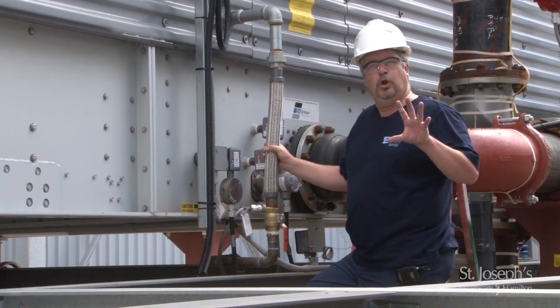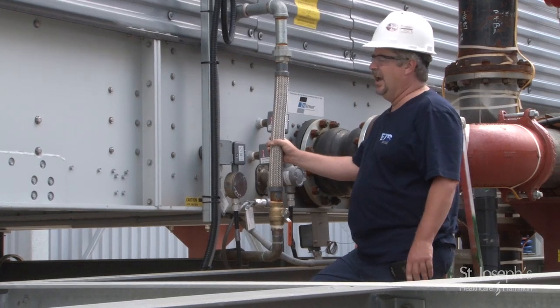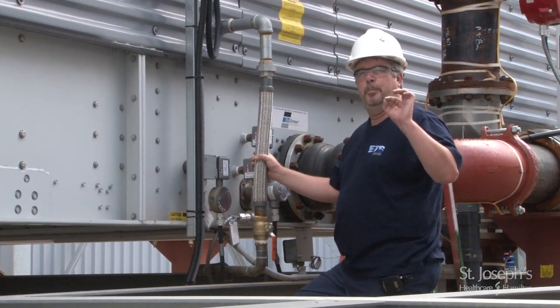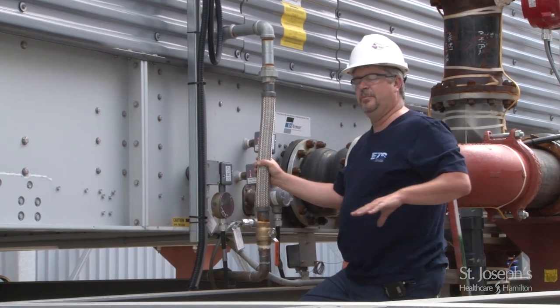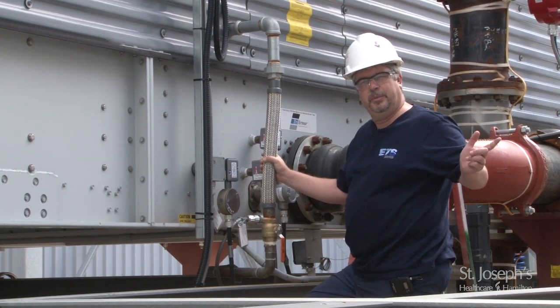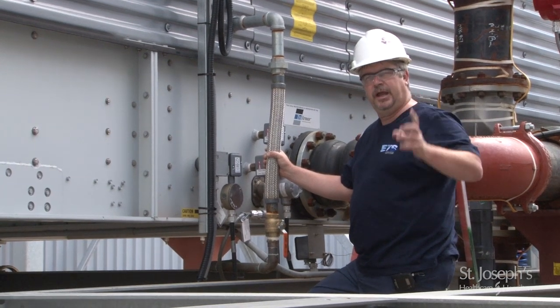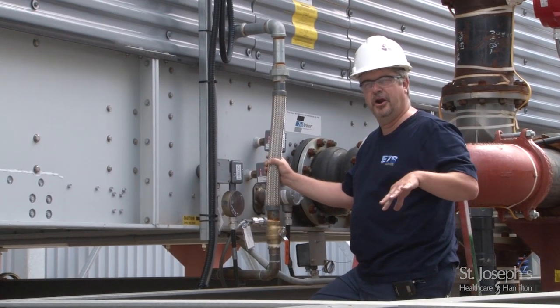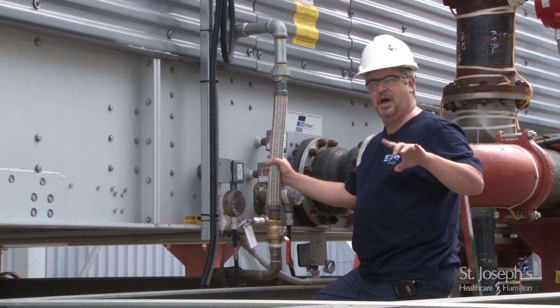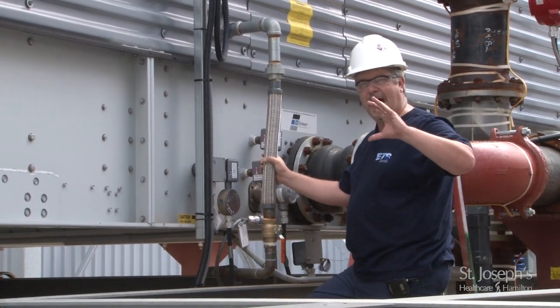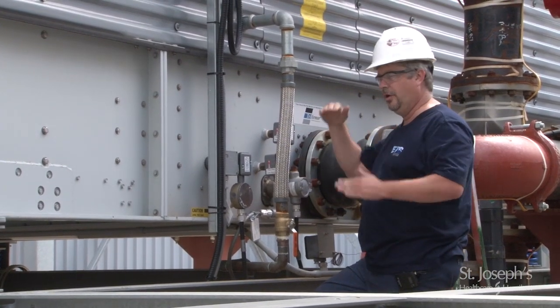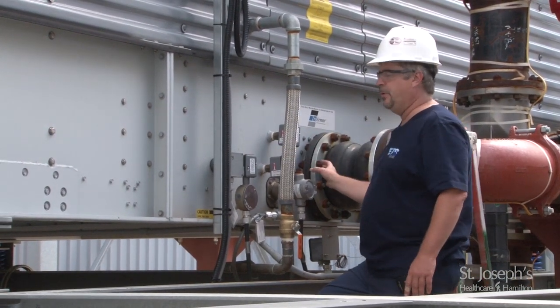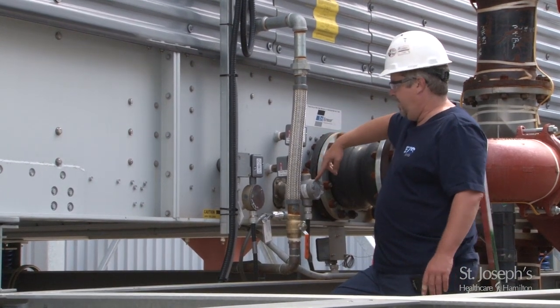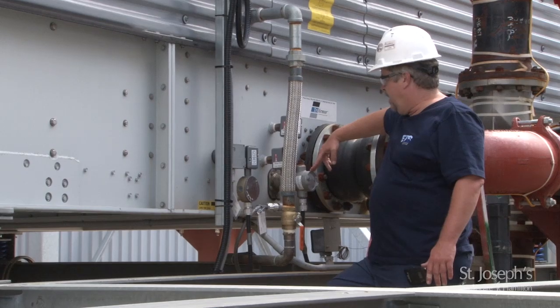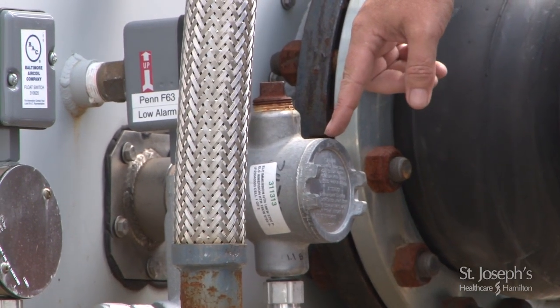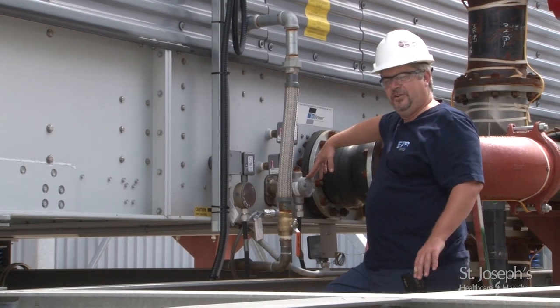Why we're so concerned about low water in these cooling towers is twofold. First, the pumps: if the water level drops too critically low, the pumps inside the mechanical room will start to suck air and not get enough water, which will cause them to cavitate and make loud banging. It's just not good. You want water levels up. It also is designed to protect the heater, and if you want to have a look right here, added to this tower is a heater. It is designed to protect this tower through winter operation.